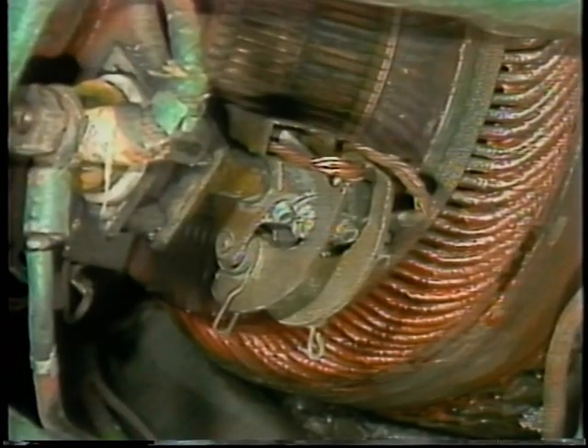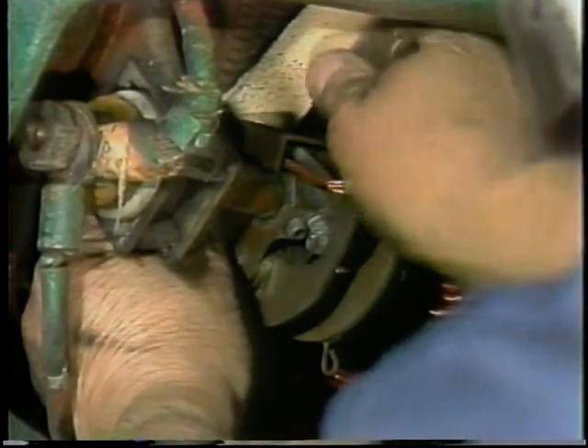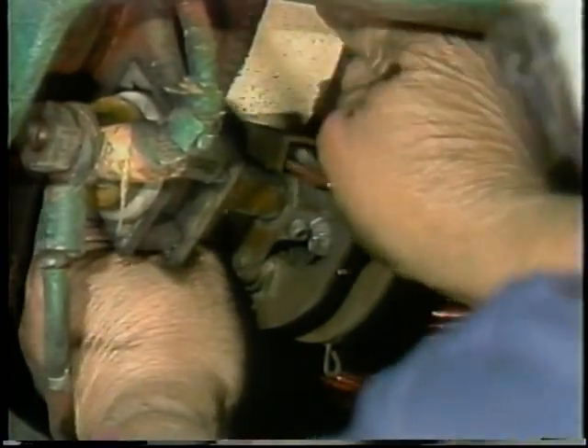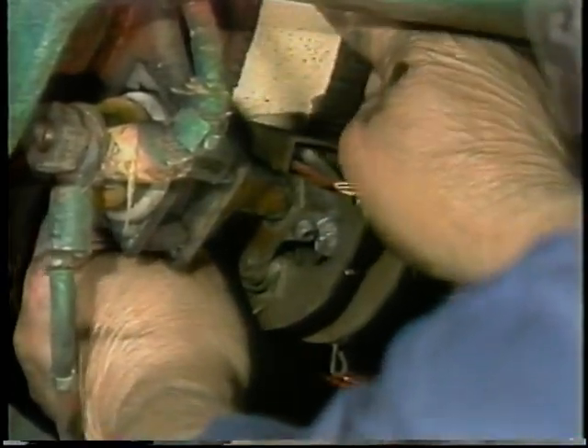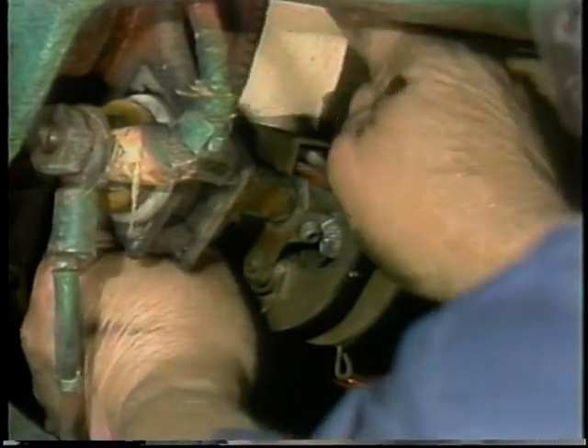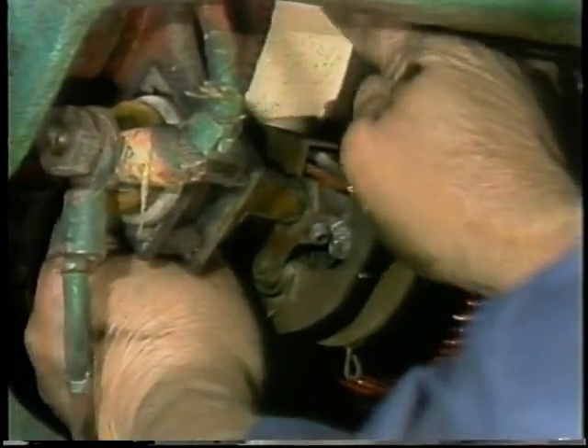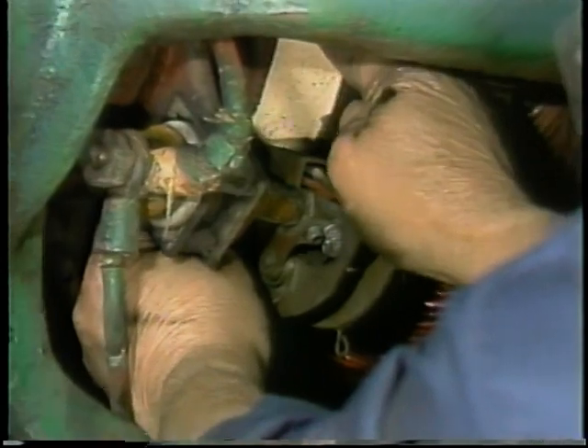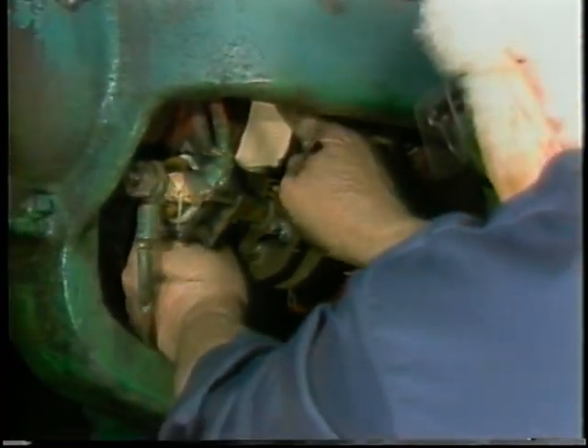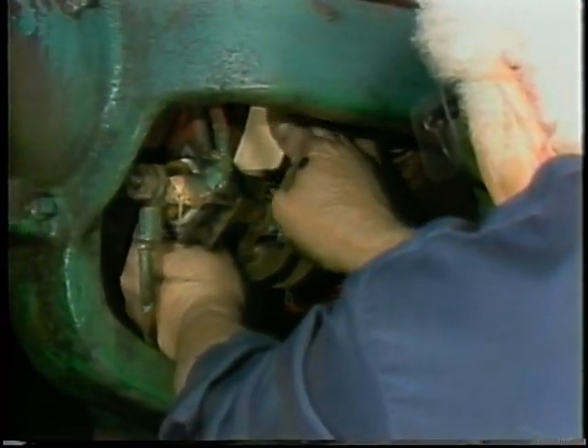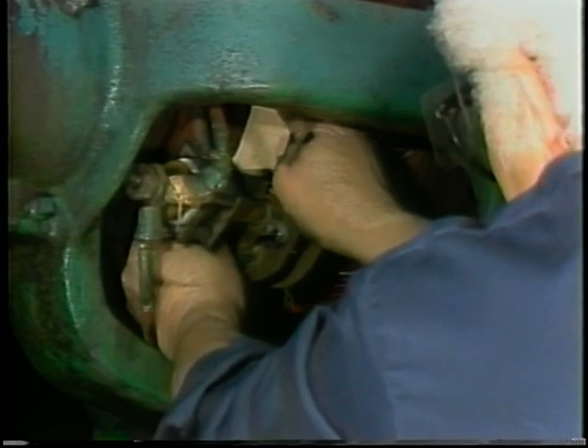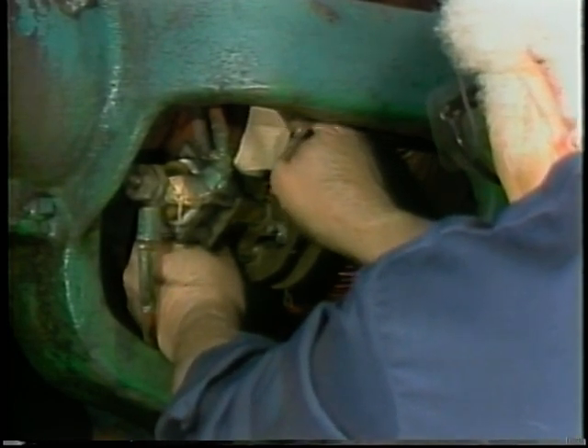Brushes usually need to be seated. In other words, they must be shaped to match the curve of the commutator exactly. The best way to do this is with a strip of fine sandpaper around the commutator. Make sure the sandpaper follows the curve of the commutator and does not round off the end of the brush. Do not use emery paper or emery cloth. The abrasive particles are conductive and could wedge in the motor, causing shorts.